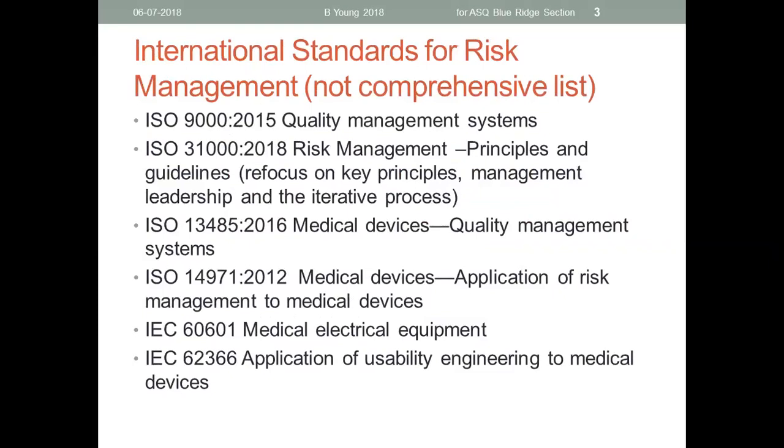There's a medical device standard, 13485, which covers the need to do risk management. ISO 14971 is a specific ISO standard for application of risk management to medical devices.